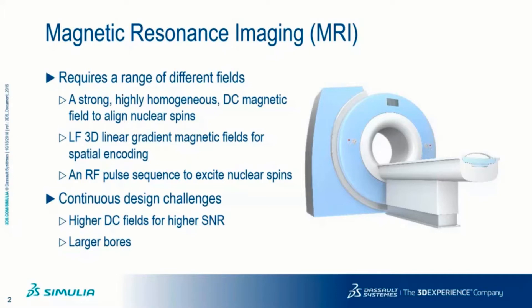There is still a lot of design ongoing and we have continuous design challenges, driven mostly by two points. On one side, we try to drive the strength of the DC static field higher and higher in order to get a better signal-to-noise ratio. At the same time, we want to make MRI examinations more convenient, so we try to get larger bores.